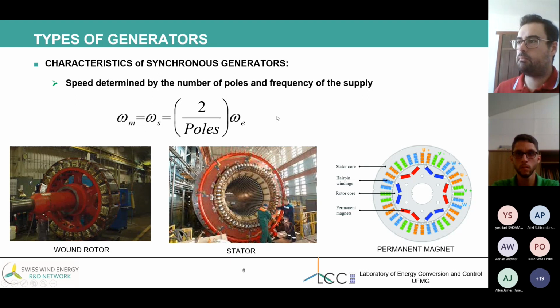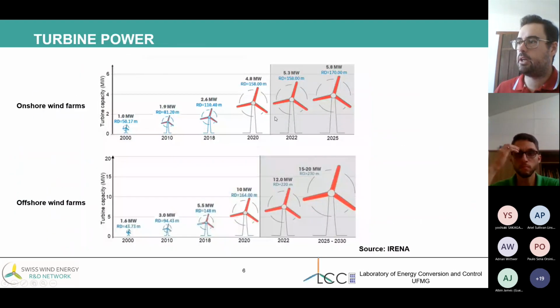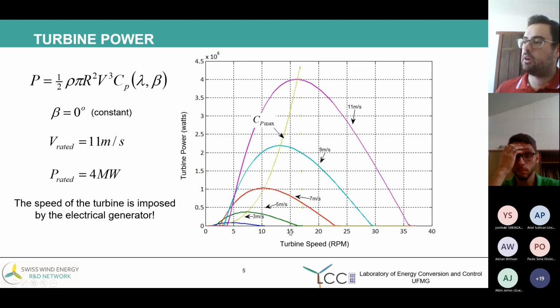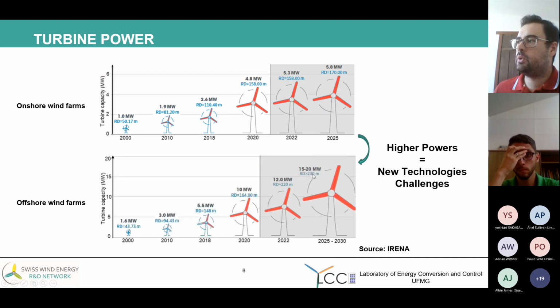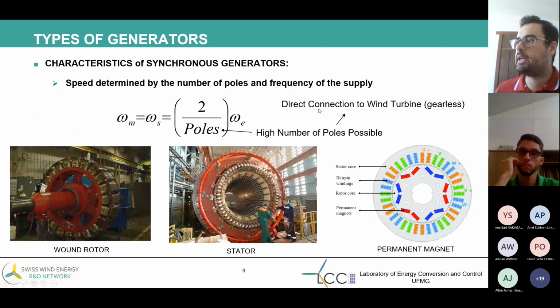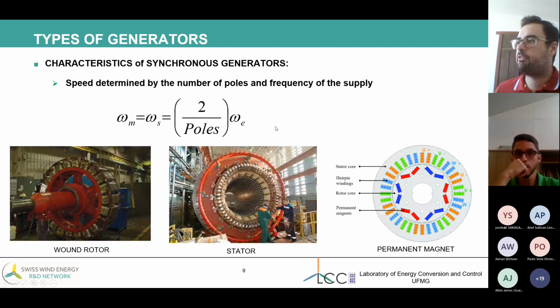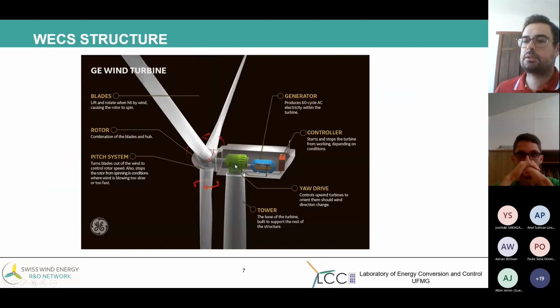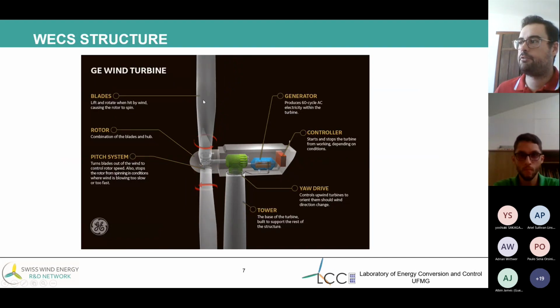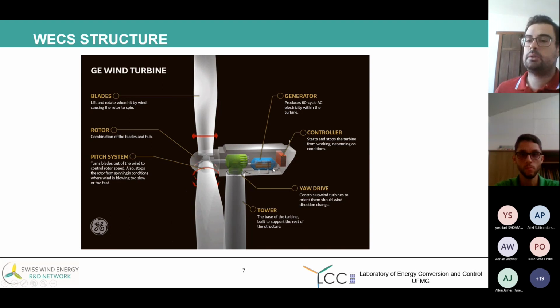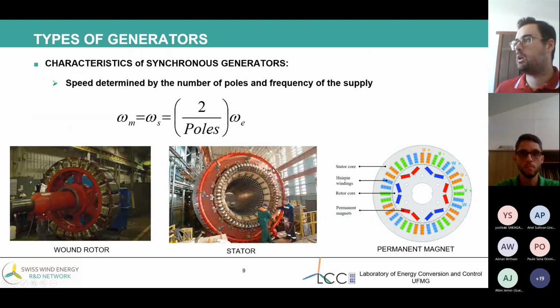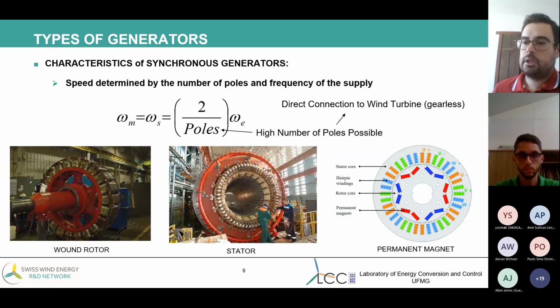We see from the mechanical curves that the speed of this kind of turbine is small, around 15 rotations per minute. When you use a machine with a high number of poles, I can avoid the gearbox. I can have a connection directly from the turbine to the generator. This is called gearless technology.